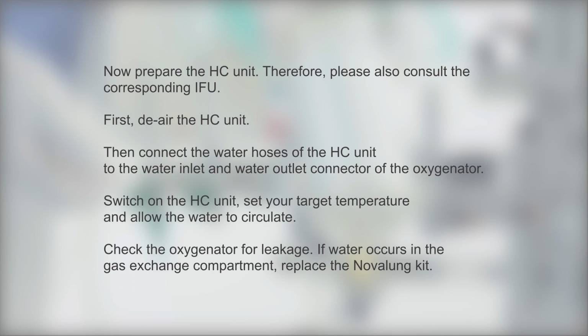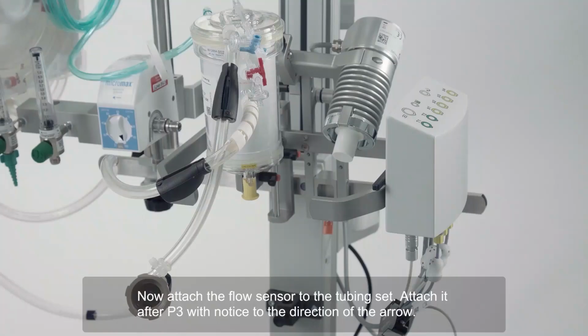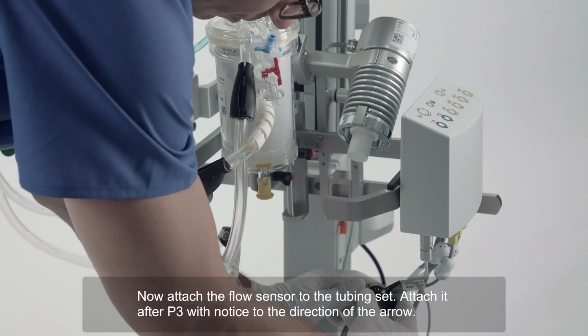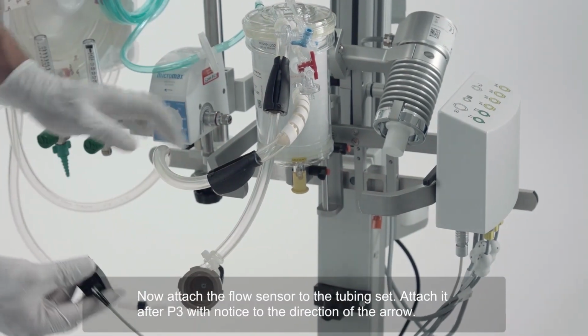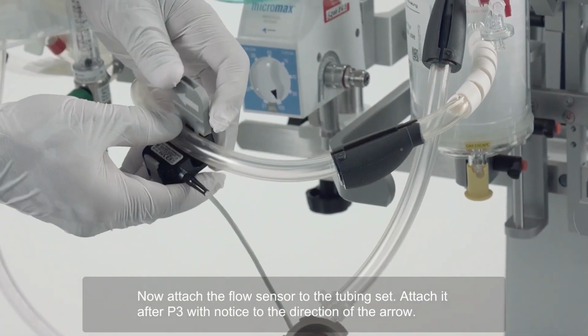Switch on the HC unit, set your target temperature, and allow the water to circulate. Check the oxygenator for leakage. If water should occur in the gas exchange compartment, replace the Novalung kit. Now attach the flow sensor to the tubing set. Attach it after P3 with notice to the direction of the arrow.